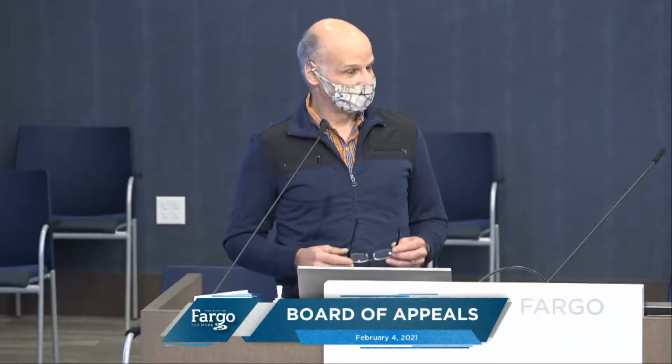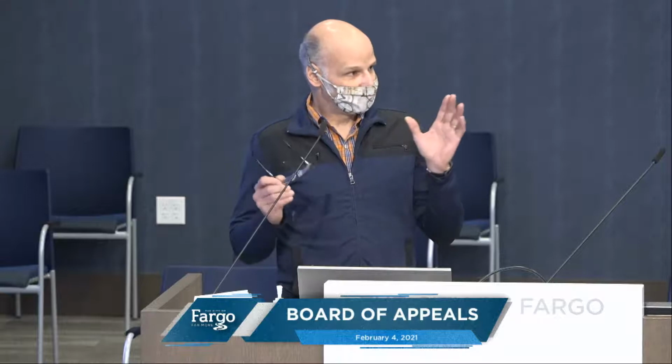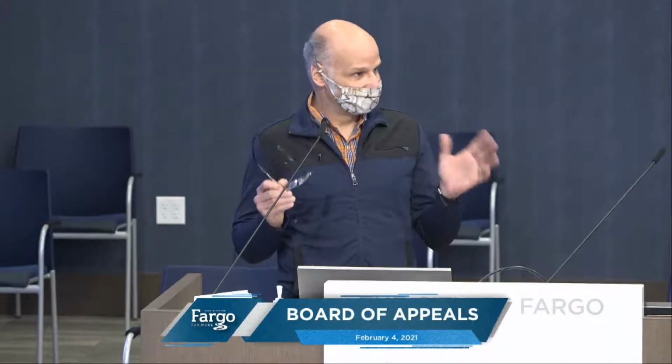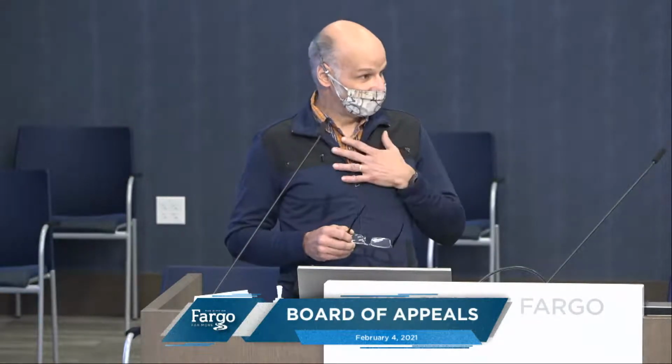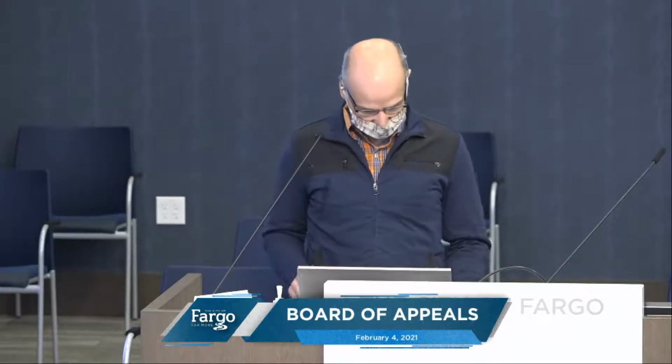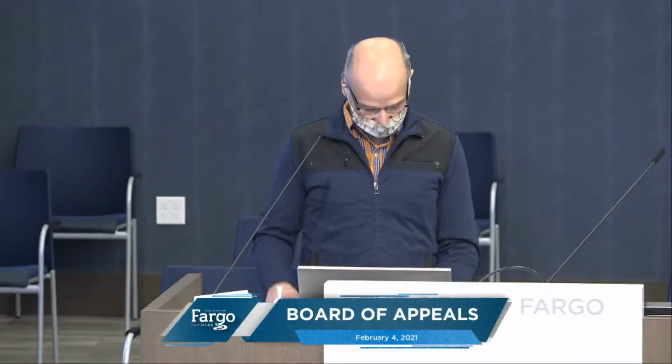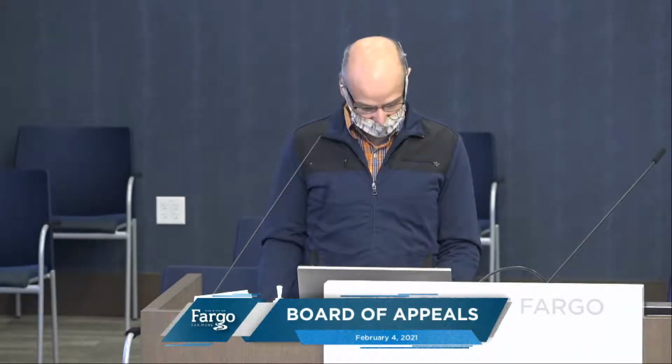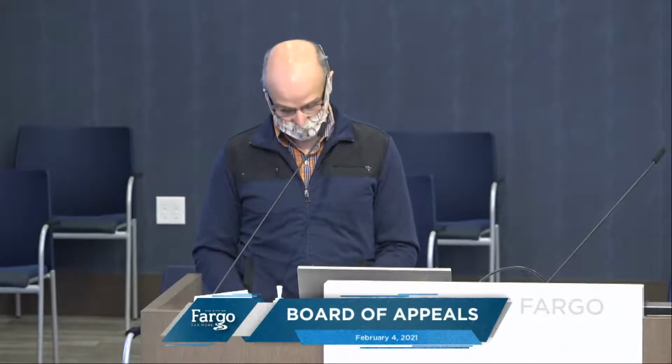Doug, you directed that question to me. How are we going to separate them? You indicated that the Group U 1,000-foot garages must be separated from each other. You asked me, how are you going to separate them? I'm saying they are separated with horizontal assemblies per section 711. Section 711 specifies that the assemblies shall be continuous without vertical openings except as permitted by this section and in section 712.